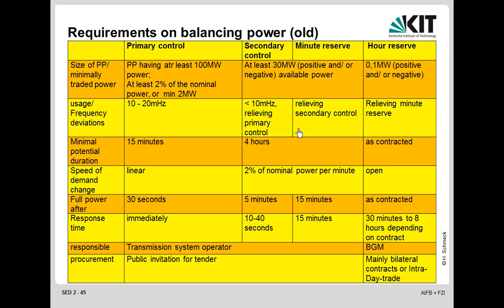And then, as I said, minute reserve is for relieving secondary control. The minimal potential duration is 15 minutes for primary control, 4 hours for secondary control, and for minute reserve and hour reserve it is as contracted, depending on what kind of contract is done with a provider of hour reserve that is actually traded on the market. And the speed of demand change is linear here. It's proportional supply of power. For secondary control, it says 2% of nominal power per minute, so it can change, but those providers of secondary control and minute reserve cannot respond as dynamically as the providers of primary control can.